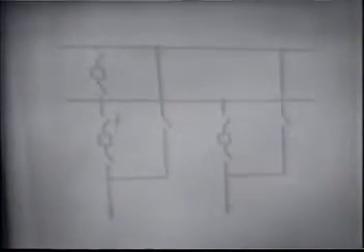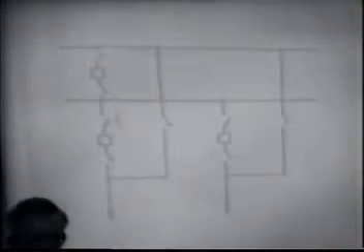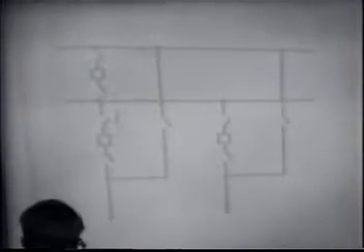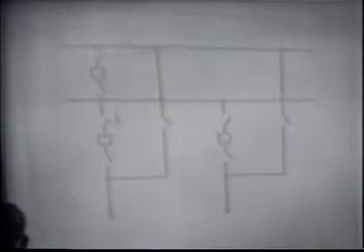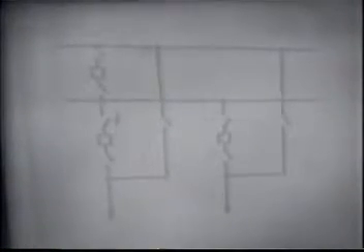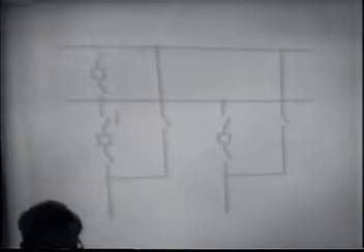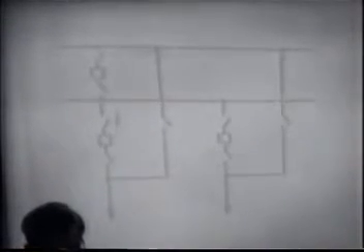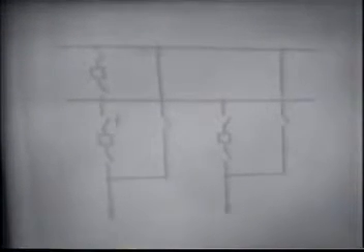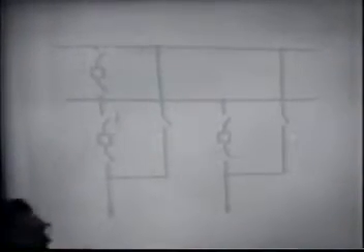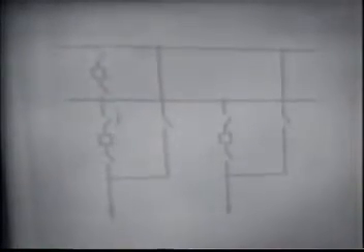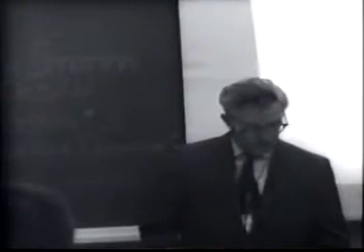The two previous bus configurations that we have talked about, the radial scheme and the ring bus, are commonly used at Iowa, Illinois. Most of our 161 kV buses are of the ring bus type. Some of our 69 kV substations and 13 kV substations are basically the single breaker, single bus type. And we have had main and auxiliary bus, or main and transfer bus schemes in the past, and I can't think of any that are active right now, although there may be some of the older ones. We did previously have some of this design.